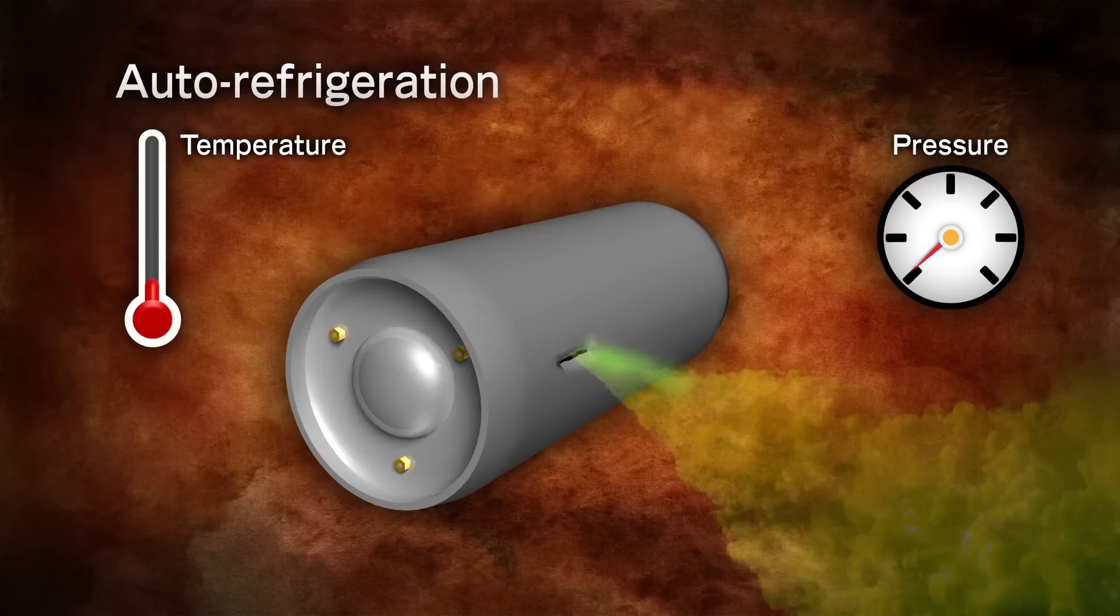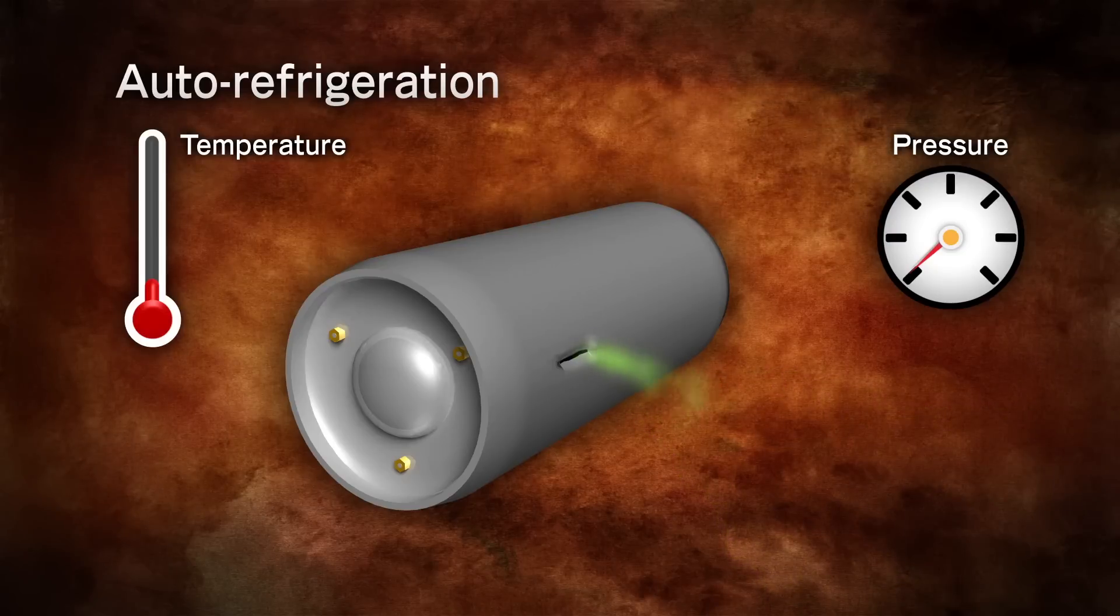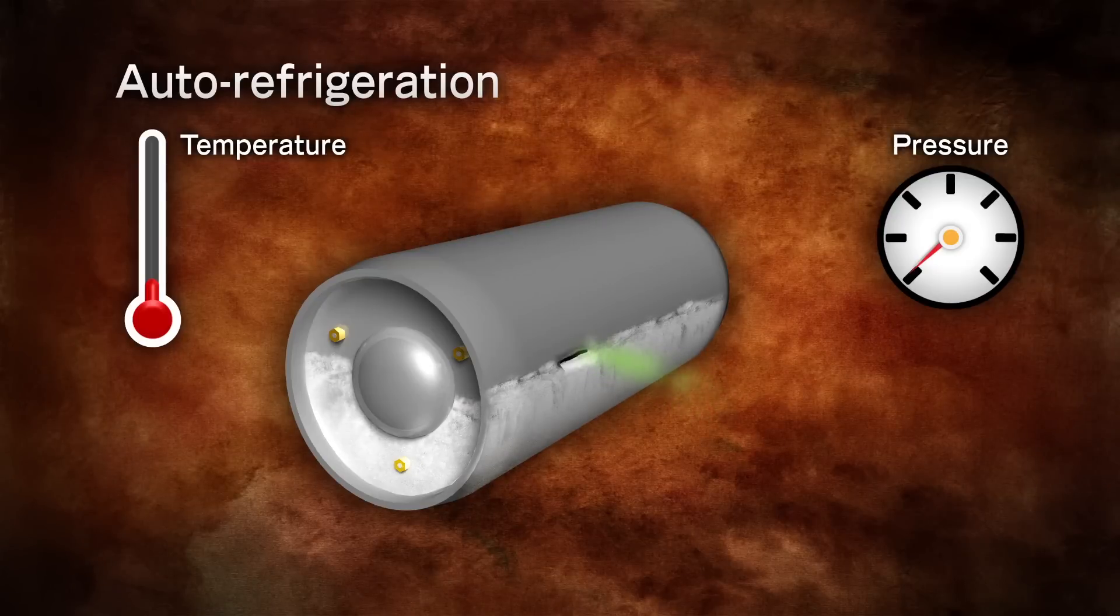It becomes colder because it is no longer under pressure from being in an enclosed container. Because the chlorine remaining in the container is so cold, a visible frost layer will form on the outside of the container at the liquid line, which is typically the level of the puncture.